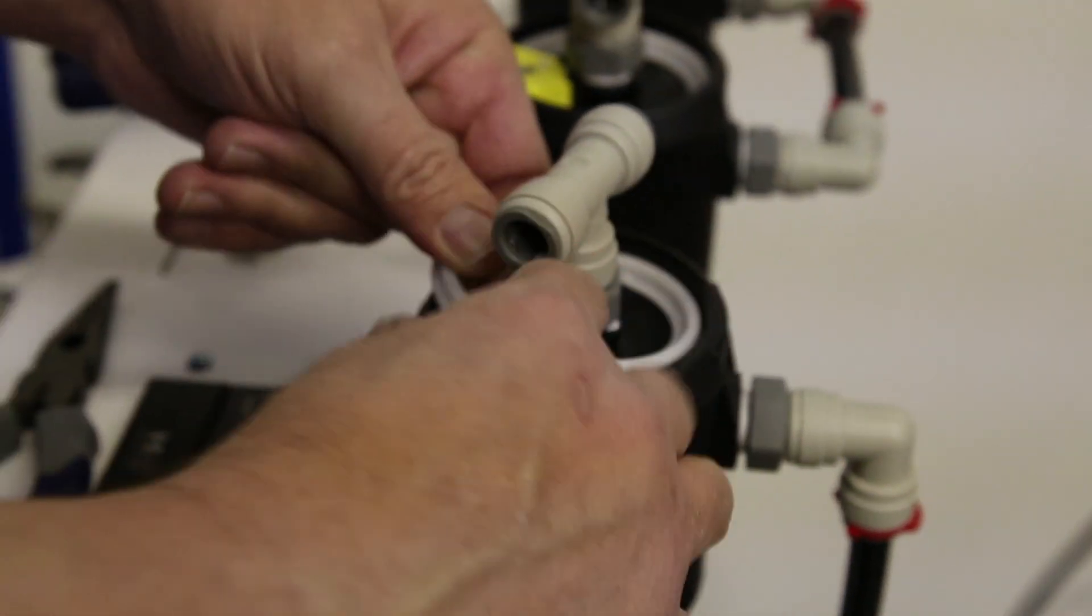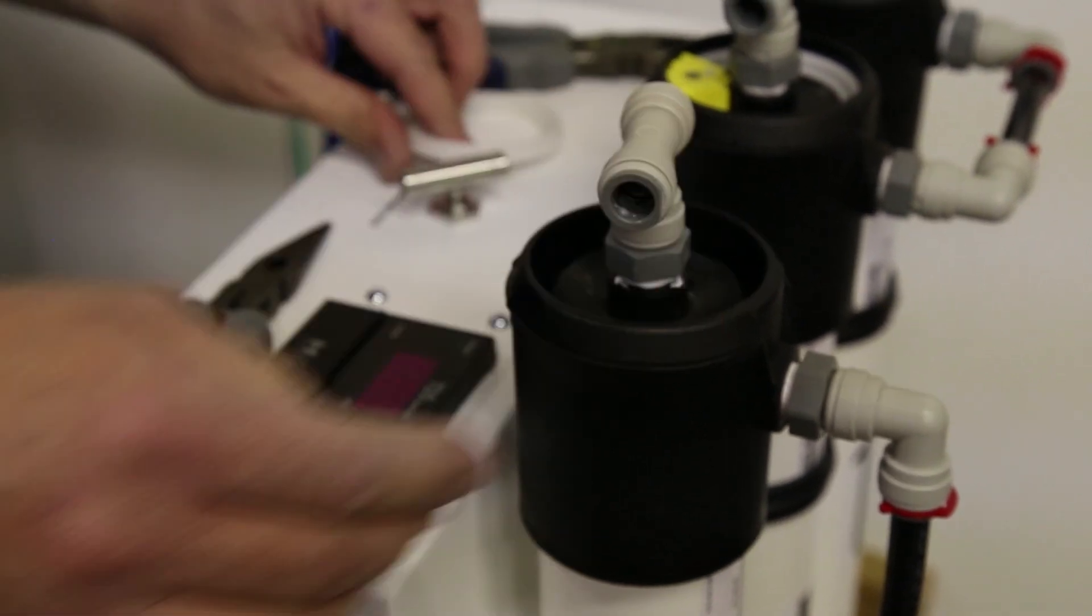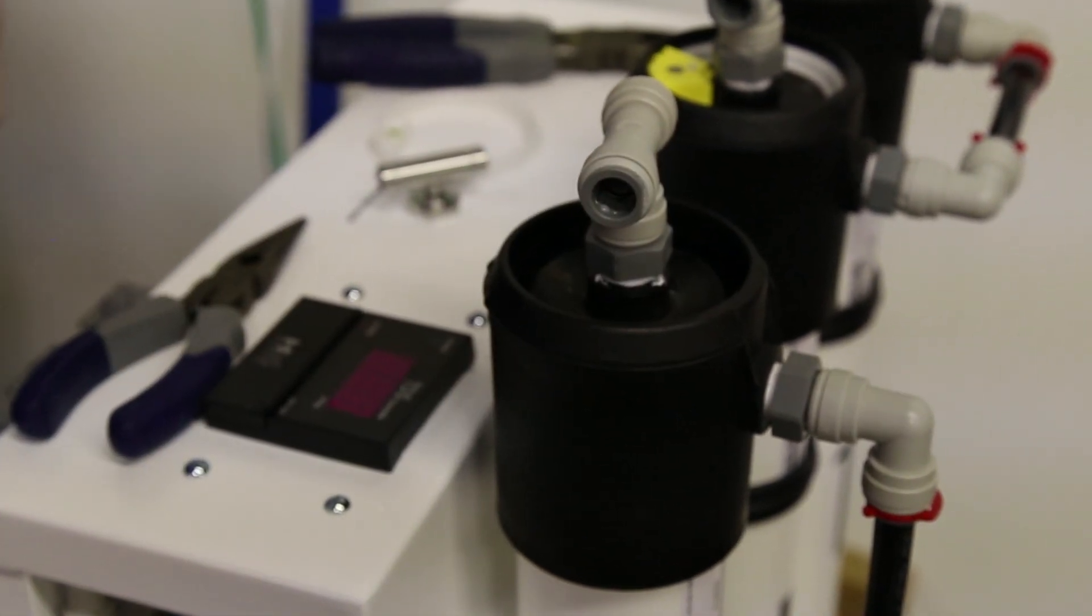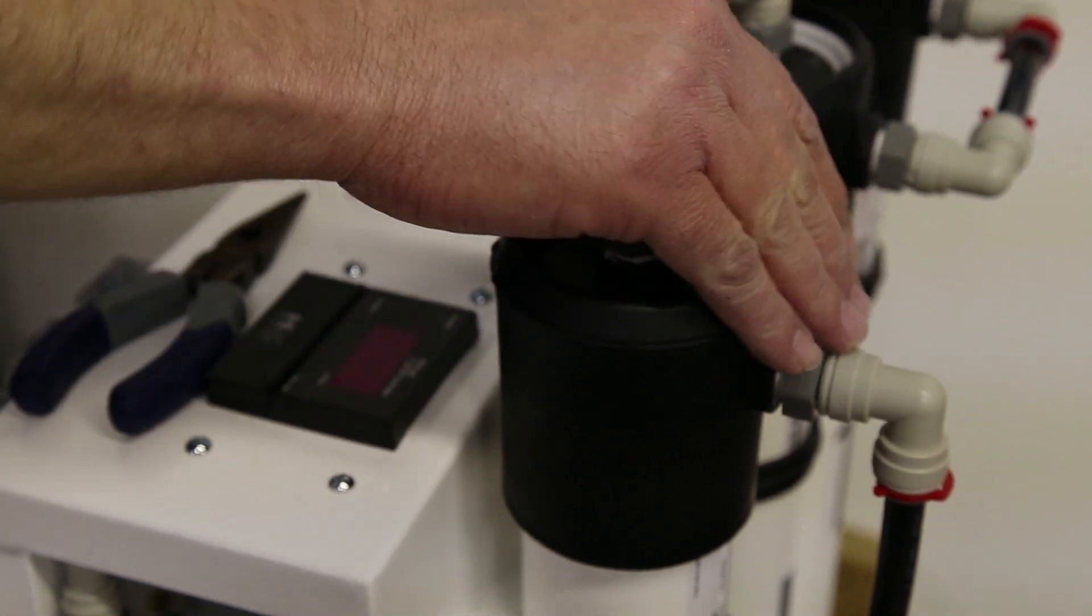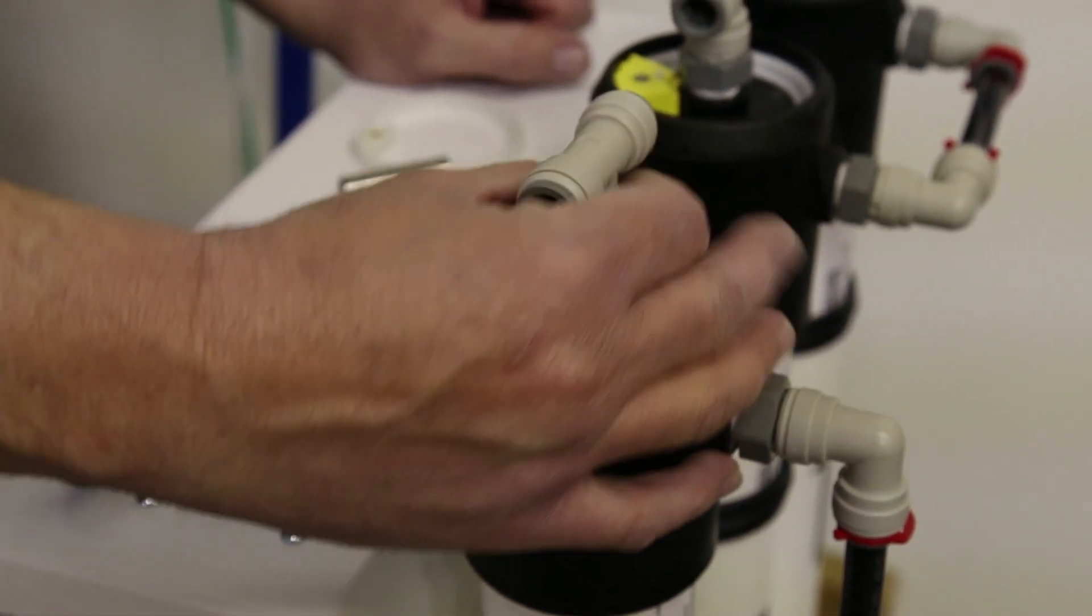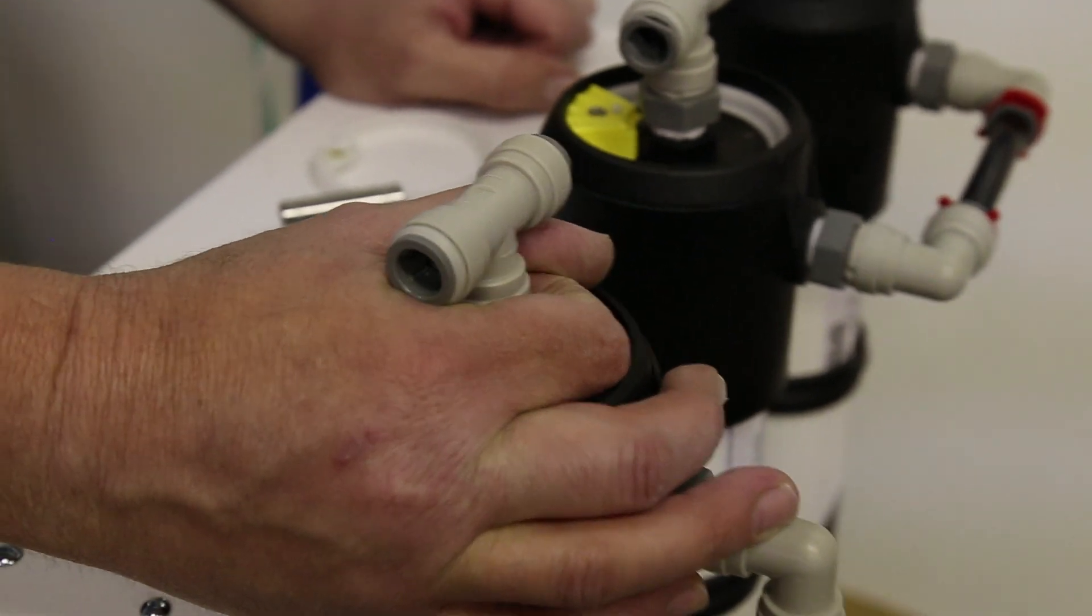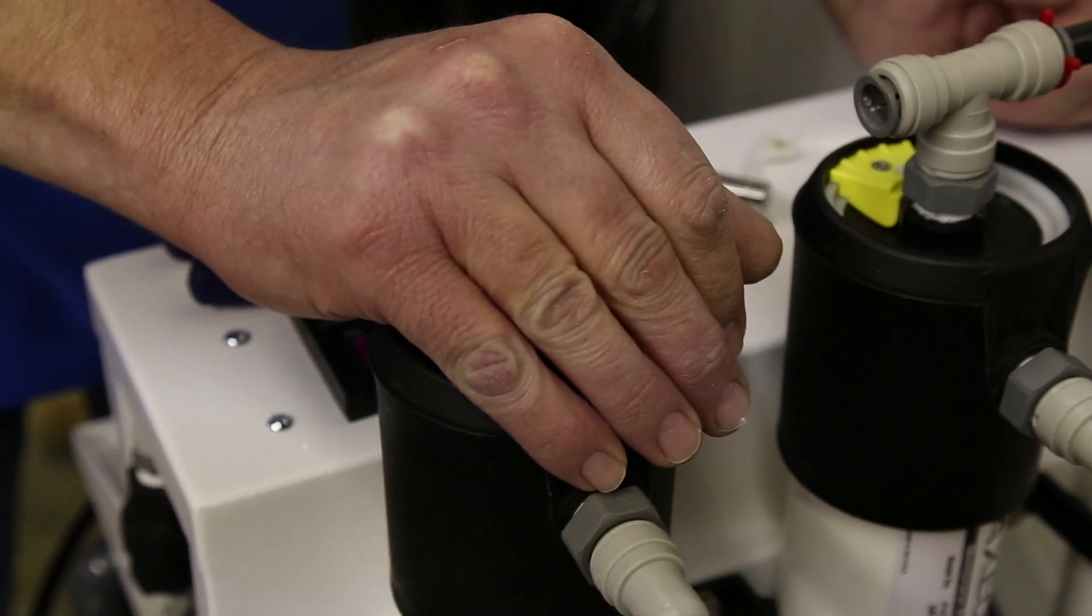Now if this is really hard to get out, check and make sure you don't have pressure on this, because there's a very good chance you may have some pressure still there. If there is pressure and you do happen to get it off, this may come out and become a projectile, so make sure the pressure is off.